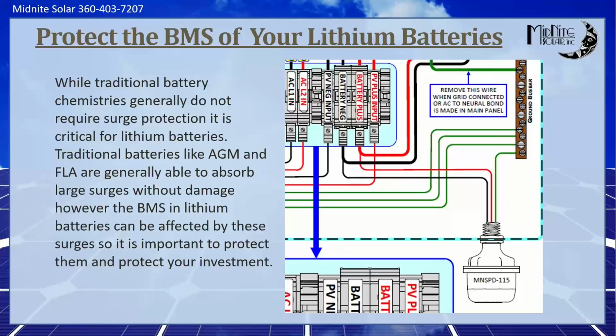Like if you're using an E panel, there's usually a very easy place to wire it up in the E panel. If you're using some other product, then you may have to be a little more creative or crimp ring terminals on, landed on some studs. Like for example, in a Sol-Ark all-in-one, you could crimp a couple ring terminals on there and throw it on the battery terminals right in the Sol-Ark if you wanted to. Or the MidNite all-in-one, you could do the same thing. A lot of different ways to skin that cat, but just go ahead and make sure you get that in there.